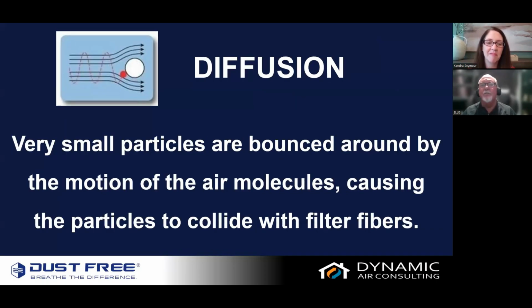Finally, diffusion. Very small particles, usually PM 2.5 or ultrafine and smaller, are bounced around with the air molecules because they're so light and influenced by the chaos going on. The particles collide with the fibers and become attached. A lot of this has to do with the thickness of a filter—you can't get a 1-inch filter to incorporate all these methods because there's just not enough media mass to create these five different methods.